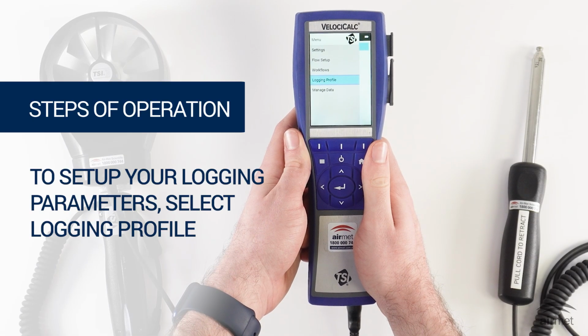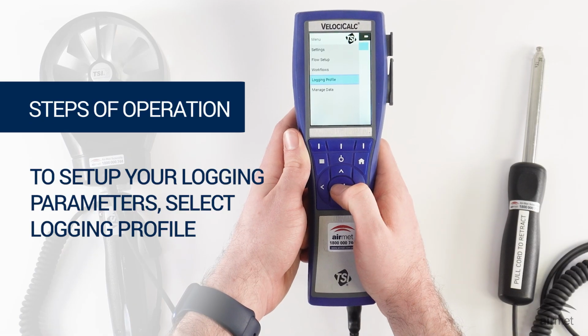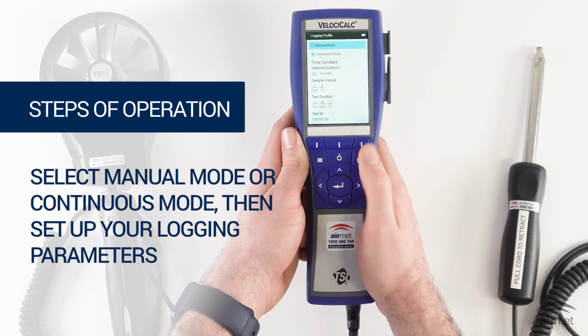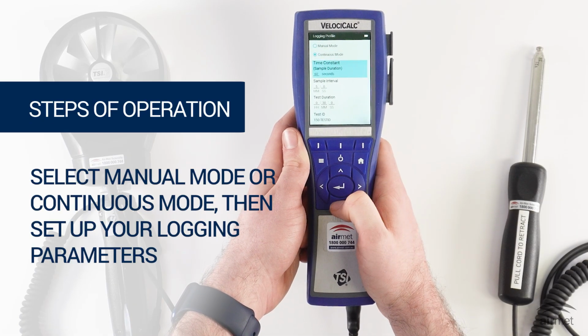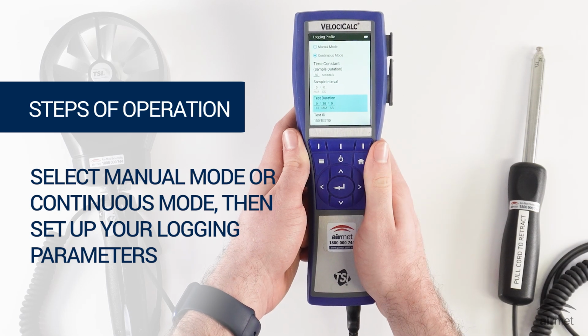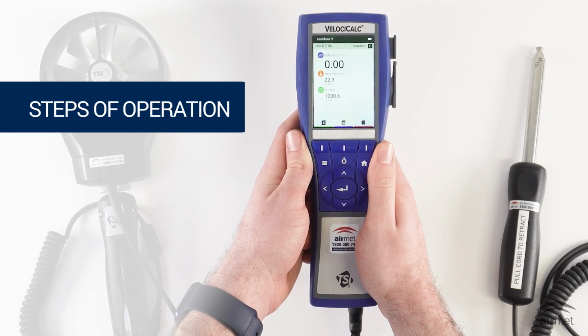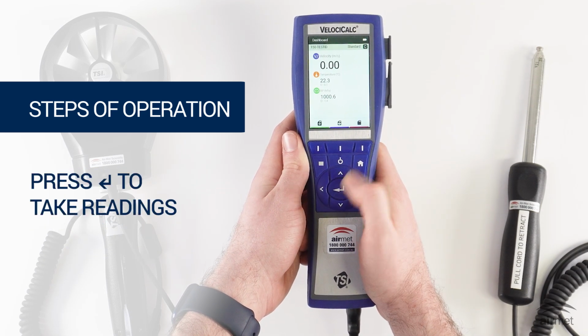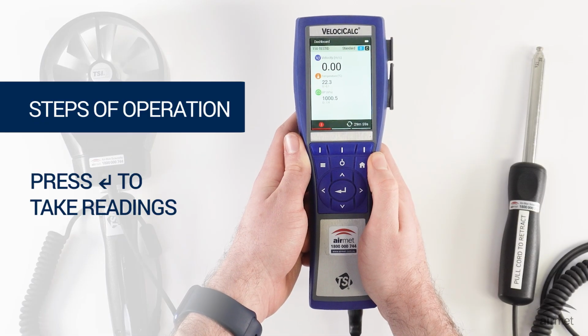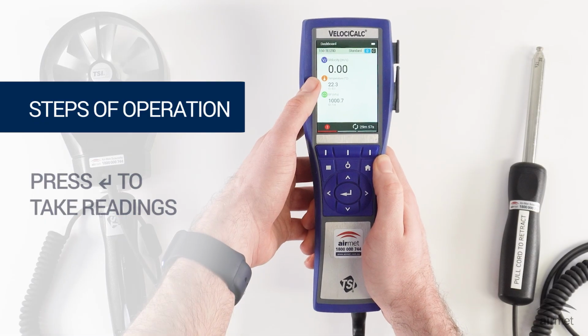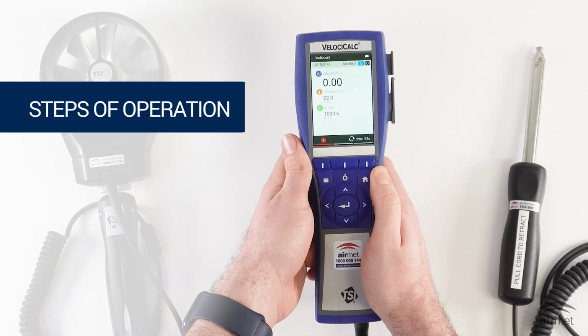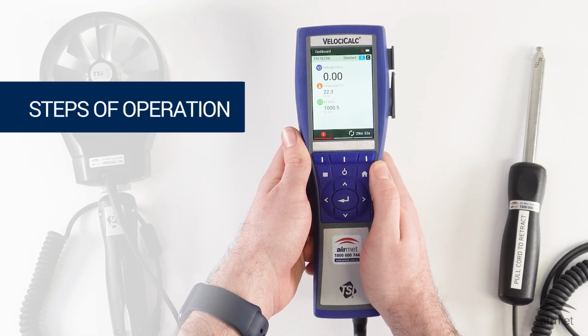To set up your logging parameters, navigate to the Logging Profile menu icon. From here, you can select from Manual or Continuous mode and set up your parameters accordingly. After your logging is set up, take readings by pressing the Enter key. The data displays in real time on the dashboard. The log will be saved as a test ID for later review and reporting.